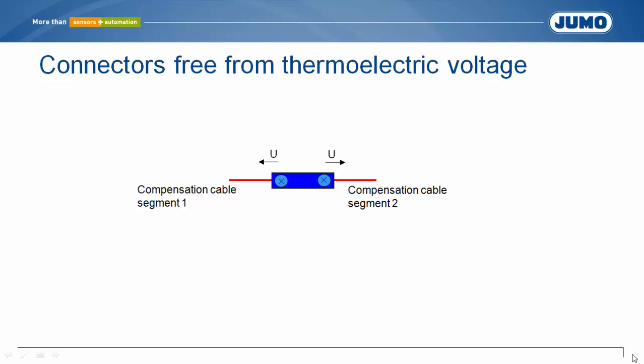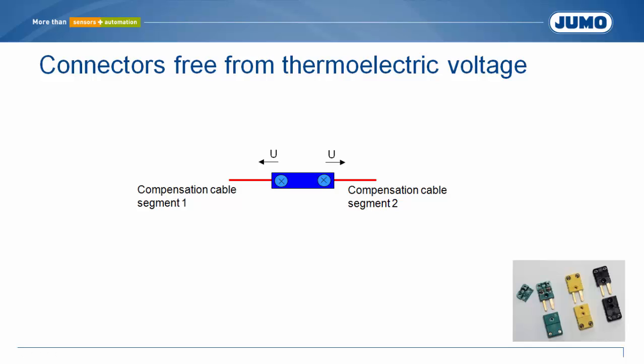Since in most cases it cannot be reliably assumed that the temperatures have the same value, it is recommended to use connectors free from thermoelectric voltage. These connectors have the same thermoelectric properties as the compensation cable, and as the name implies, no thermoelectric voltage is produced. The particular connector for the thermocouple in use must be chosen, and the polarity must be considered.